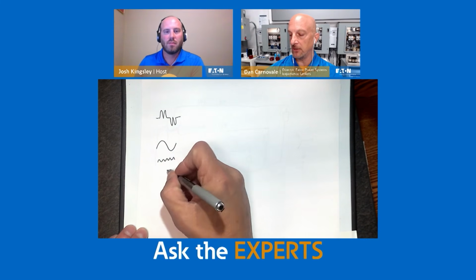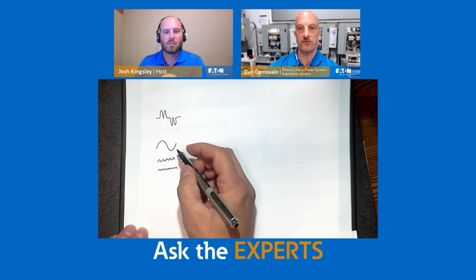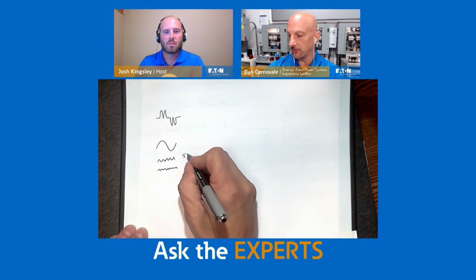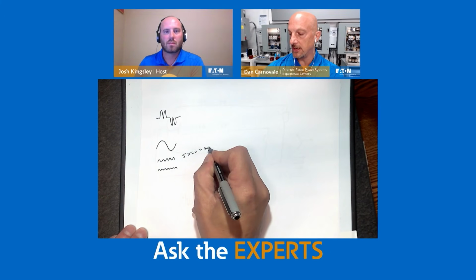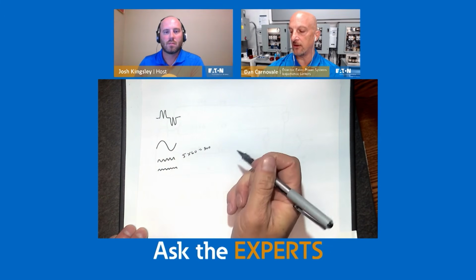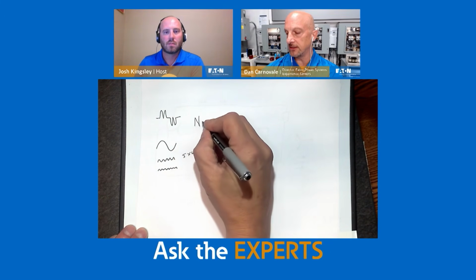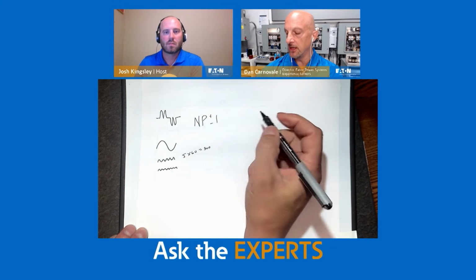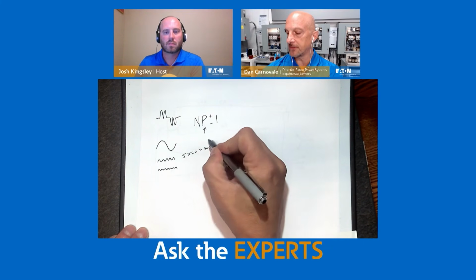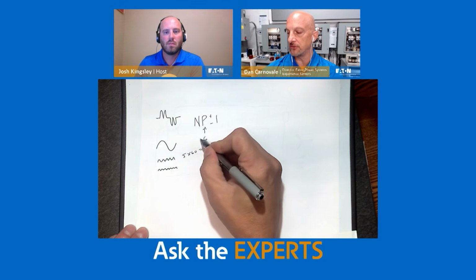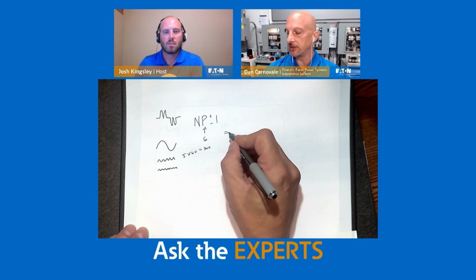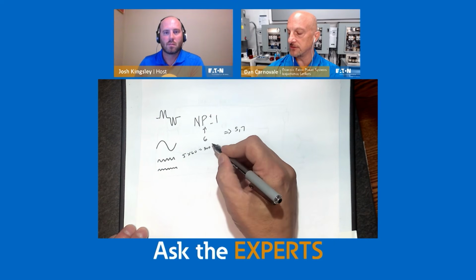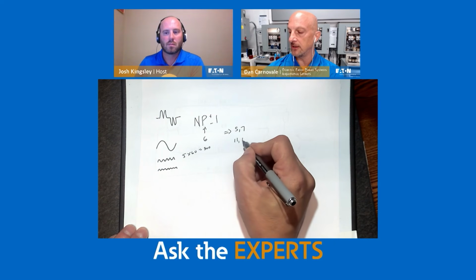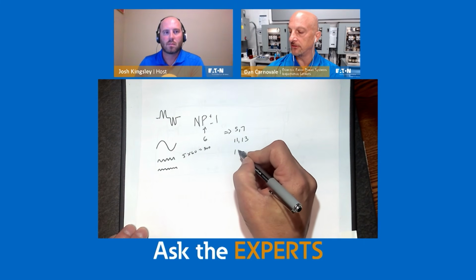It might have a fifth harmonic and it might have a seventh harmonic. And you say, well, how do you know which frequencies those are? Fifth harmonic is 5 times 60, or 300 hertz. How do you know what that waveform would have? There's a nice, easy calculation here: it's N times P plus or minus 1. So with 6 pulse drives, P is 6, and N is just an integer: 1, 2, 3, 4, 5. So 1 times 6 plus or minus 1 gives us 5th and 7th, and 2 times 6 plus or minus 1 gives us 11th and 13th, and 3 times, so 17th and 19th.